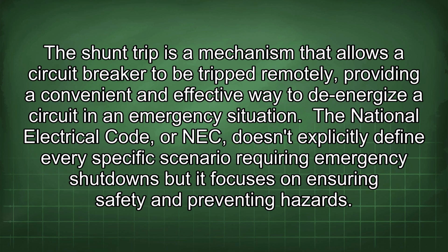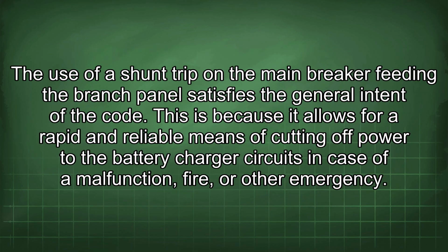The National Electrical Code, or NEC, doesn't explicitly define every specific scenario requiring emergency shutdowns, but it focuses on ensuring safety and preventing hazards. The use of a shunt trip on the main breaker feeding the branch panel satisfies the general intent of the code. This is because it allows for a rapid and reliable means of cutting off power to the battery charger circuits in case of a malfunction, fire, or other emergency.